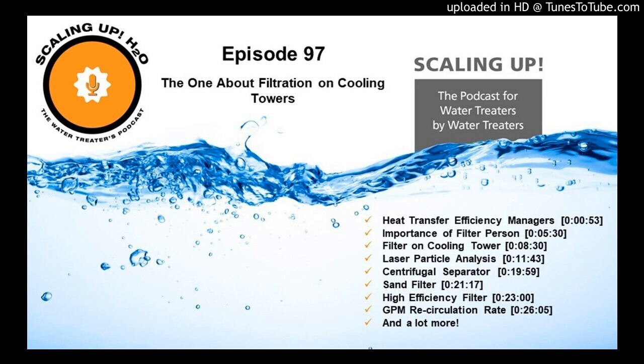When media is replaced every maybe 10 years or whatever, we generally take an industrial vacuum cleaner and suck the media out of there while the water is still wet. Open the cap, let off the pressure, let it drain down to near the top surface of the media, and you use an industrial vac and you suck the stuff out of there and put it in drums or barrels or whatever and dispose of it. And then the new media is poured back into the filter. We do that a lot. It's not a particularly big project.